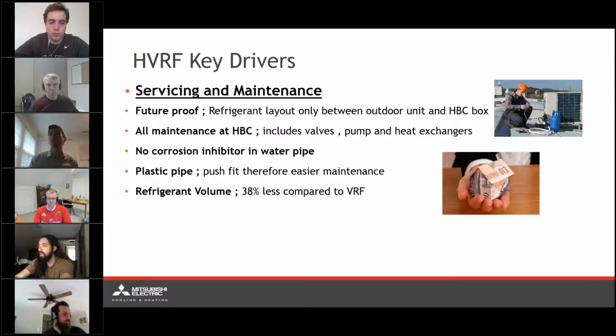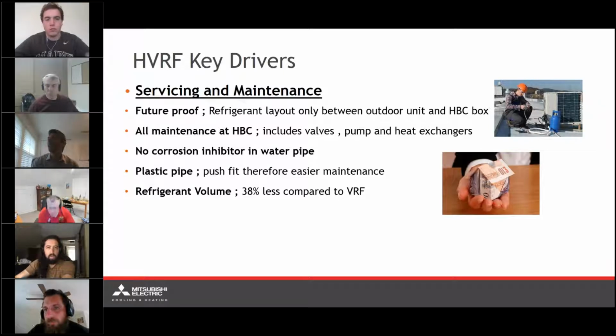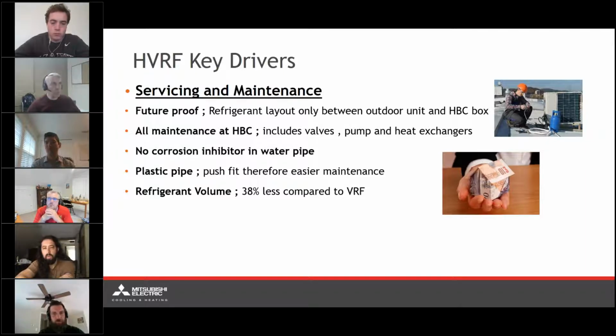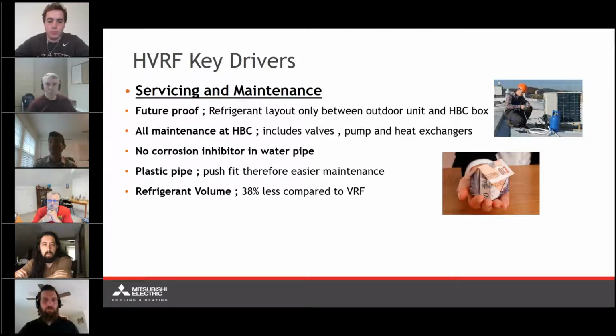And some of the major questions we see about the future developments of VRF in order to make it easier on the installer, easier on the service guys. One thing I hear time and again, and I could argue it to death, but I get a question. I get comments all the time. Yeah, they're leaky systems. VRF is leaky systems. And I ask, okay, where's it leaking? Is it leaking in the condenser unit? No. Is it leaking in the fan coil? No. I'm like, okay, well, in the system as a whole, I mean, I don't know what to tell you as the manufacturer, but there's only so many times you could say that before someone just says, well, they're prone to leaks, so ultimately maybe we should go with a different system. So that's a valid concern. So we're reducing the amount of potential for refrigerant leaks and ultimately eliminating that particular problem.